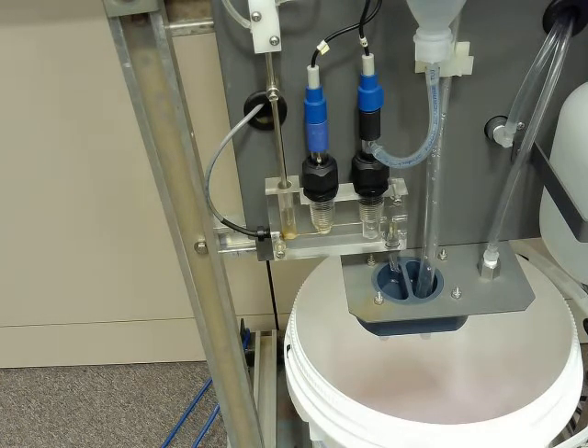So there's a few things that can interfere with that reading. The probe is, the membrane of that glass is ion specific to sodium. So the only ion that it should let through is a sodium ion. The only ion really smaller than a sodium ion is your H+ ion. So obviously that one can interfere with our reading, the one that can kind of get through that membrane.